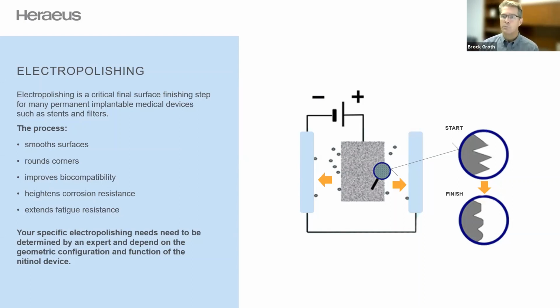The other thing that this material removal will cause is, with things like a stent, when it's laser cut, you'll have fairly square strut elements. More material will be removed from the corners, and you will round the corners. One of the other benefits that electropolishing will give you is improved biocompatibility. This will happen through several mechanisms. This removal of material will give you a nice surface finish that will create less trauma to the tissue it's coming in contact with, but electropolishing will also lay down a thin adherent oxide layer, and this will improve your corrosion resistance.